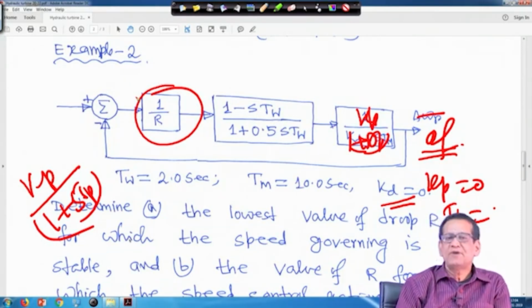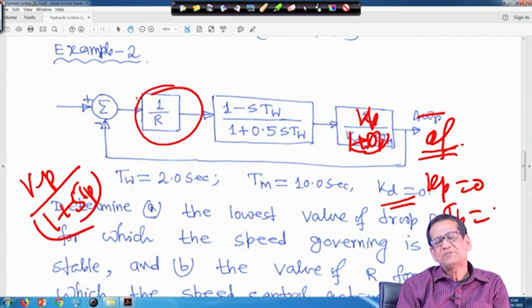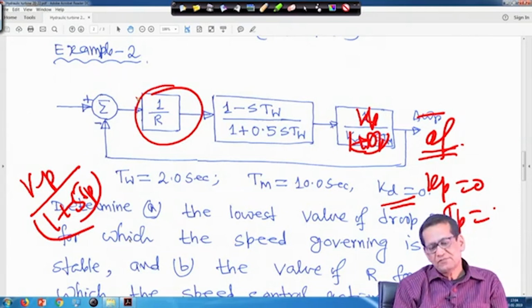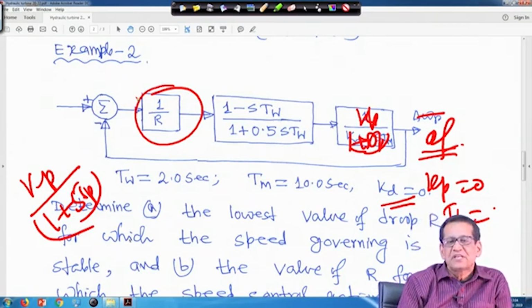It varies from unit to unit, steam turbine to steam turbine, but generally it is 3% to 10% per minute. For a steam turbine, the generation rate increasing or decreasing is more or less the same.